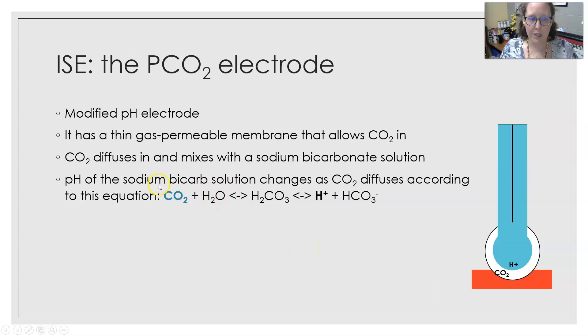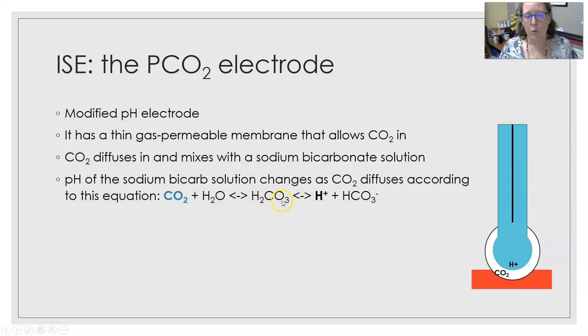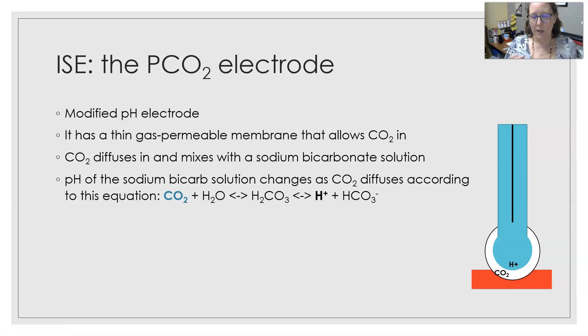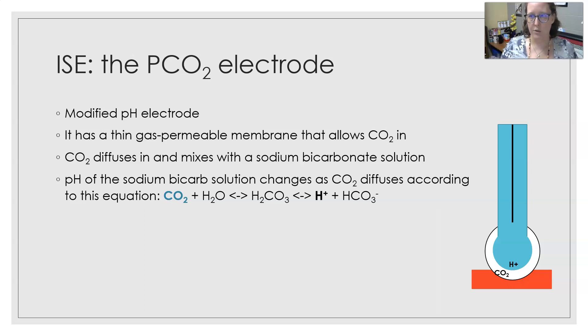The equation occurring in this part of the electrode is: CO2 picks up a molecule of water to become carbonic acid, which then dissociates into hydrogen ions and bicarbonate. So for every molecule of CO2 that crosses over, a hydrogen ion is produced. The more hydrogen ions produced, the more cross the membrane. From this, you can equate the pH change to the CO2 concentration.